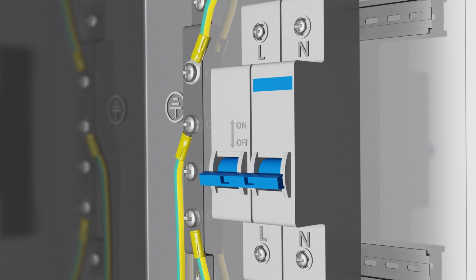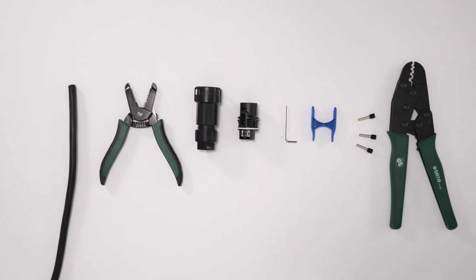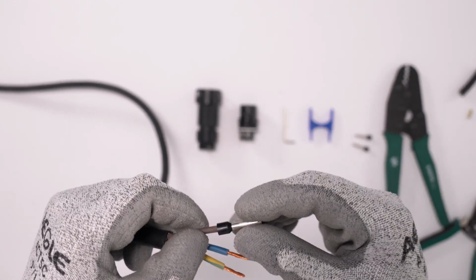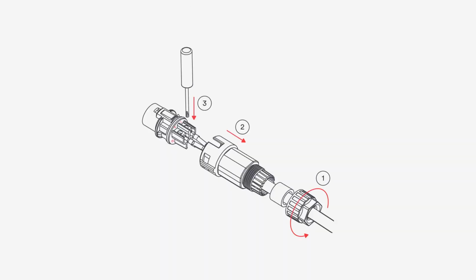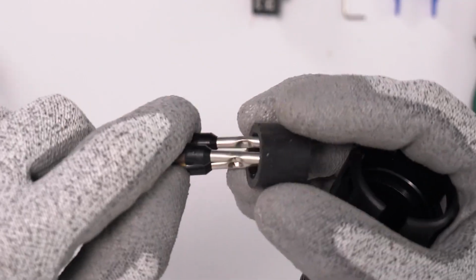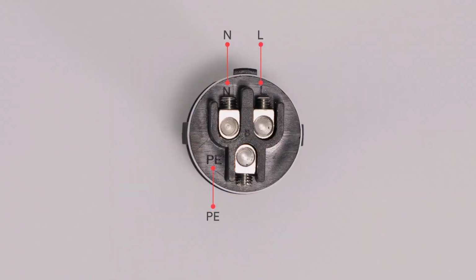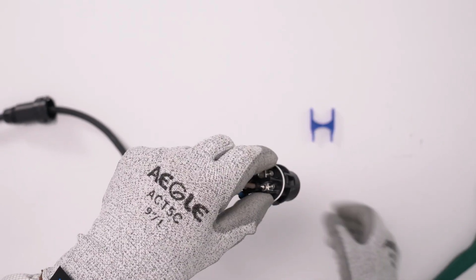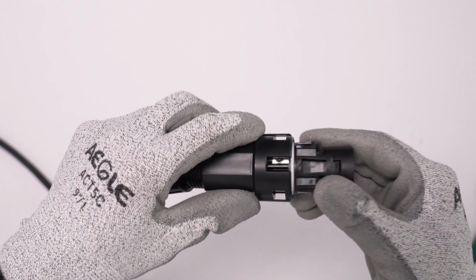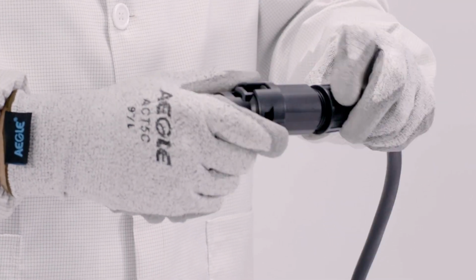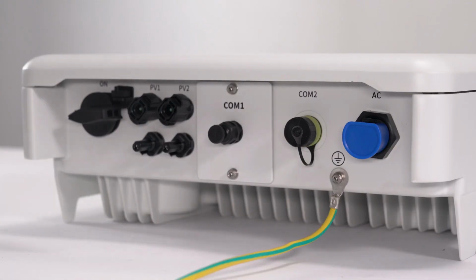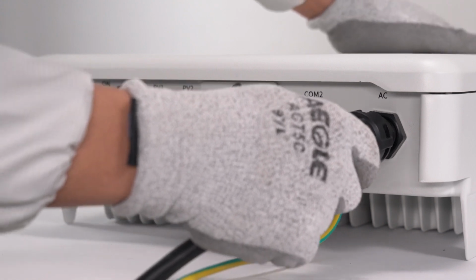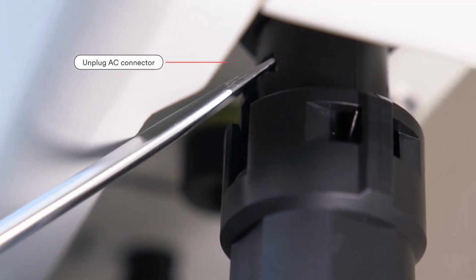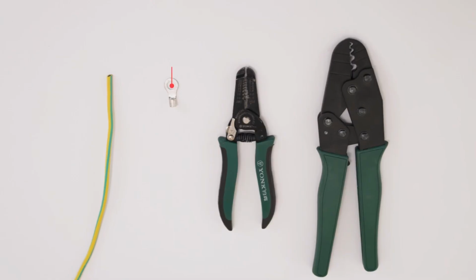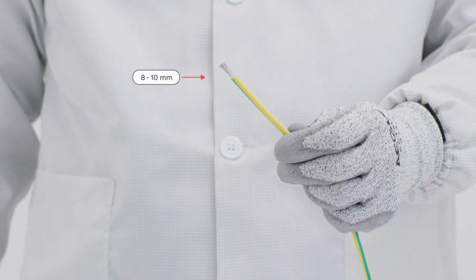Switch off the miniature circuit breaker and ensure it against being inadvertently switched back on. AC cable requirements are as follows. Loosen the swivel nut of the AC connector. Insert the crimped conductors into corresponding terminals. And tighten screws with the accompanying Allen key. Insert the adapter to the socket element. Stuff the seal ring into the adapter and tighten the swivel nut. Plug the AC connector into the socket for the AC connection. If required, you can connect a second protective conductor as equipotential bonding.